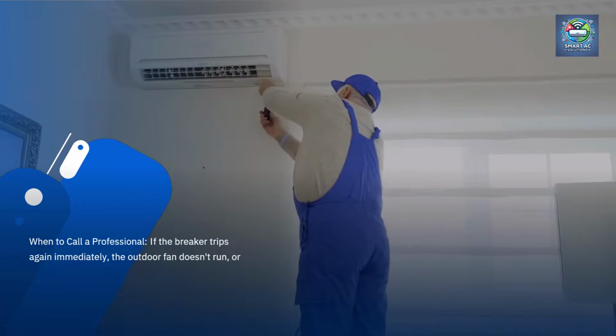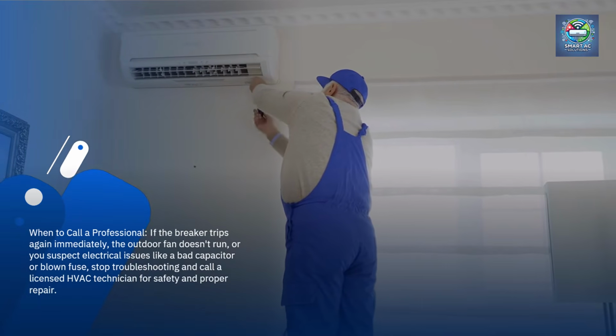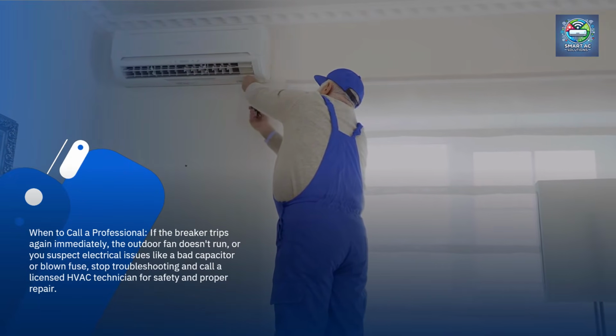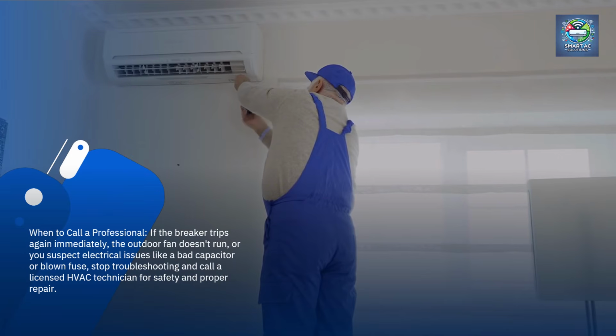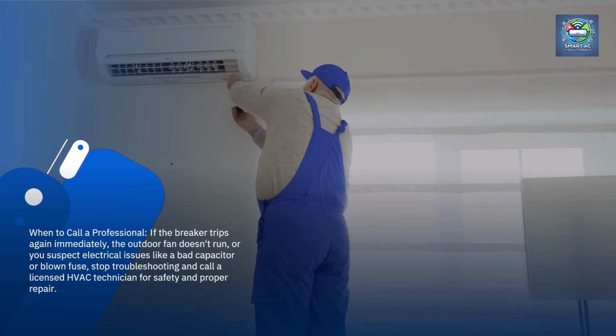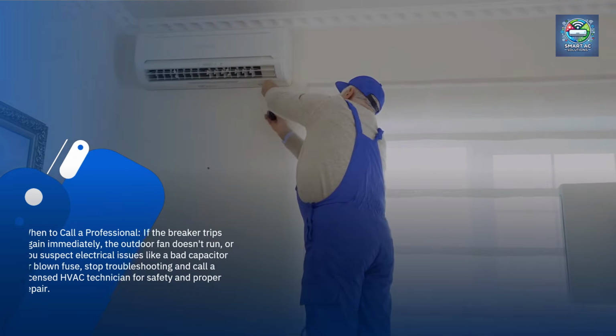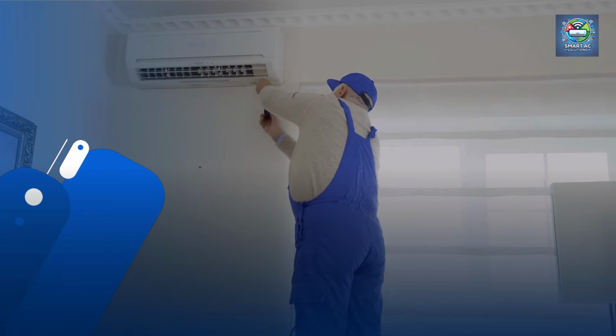When to call a professional. If the breaker trips again immediately, the outdoor fan doesn't run, or you suspect electrical issues like a bad capacitor or blown fuse, stop troubleshooting and call a licensed HVAC technician for safety and proper repair.